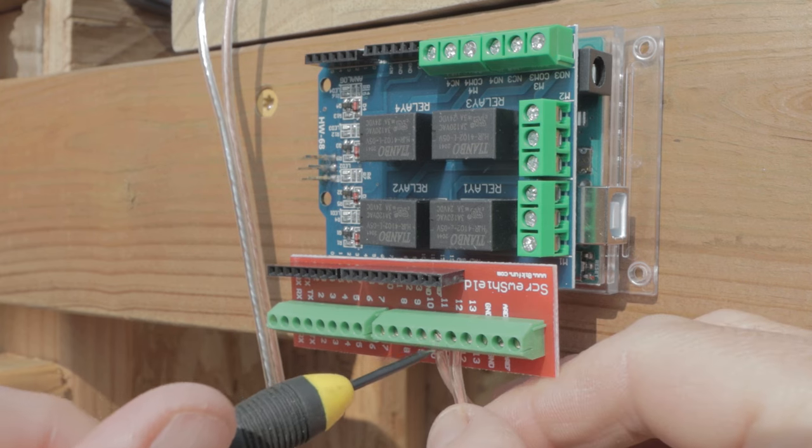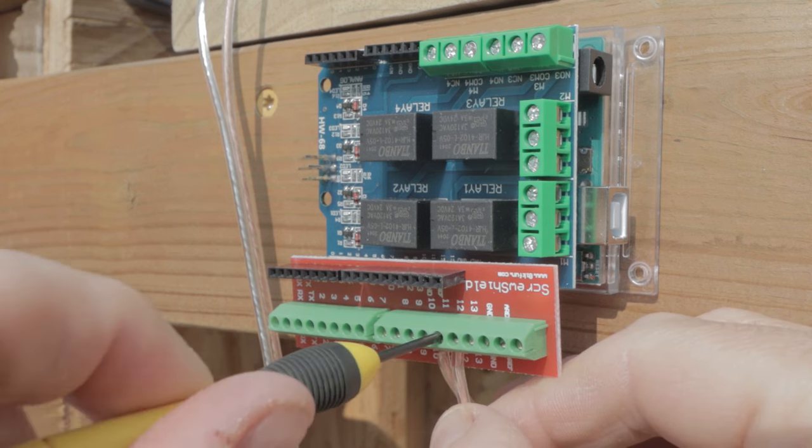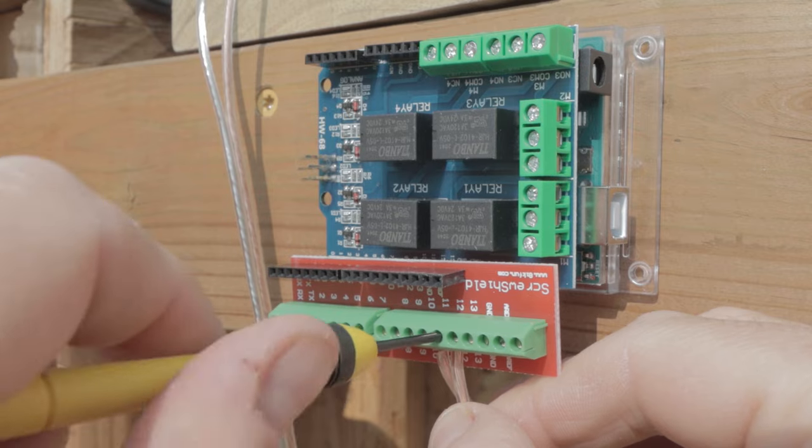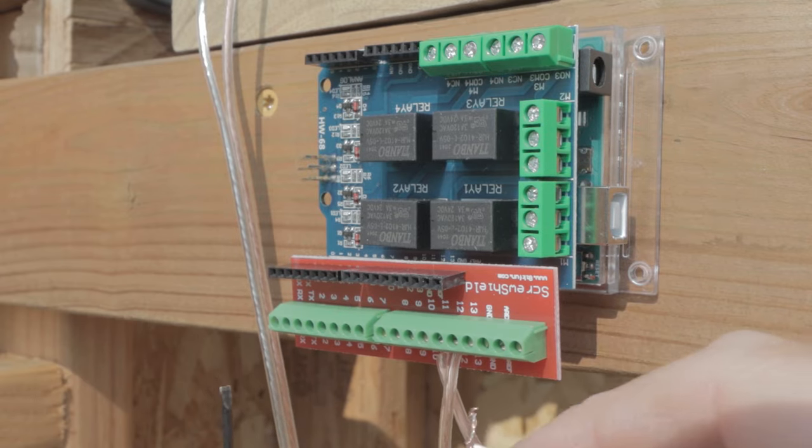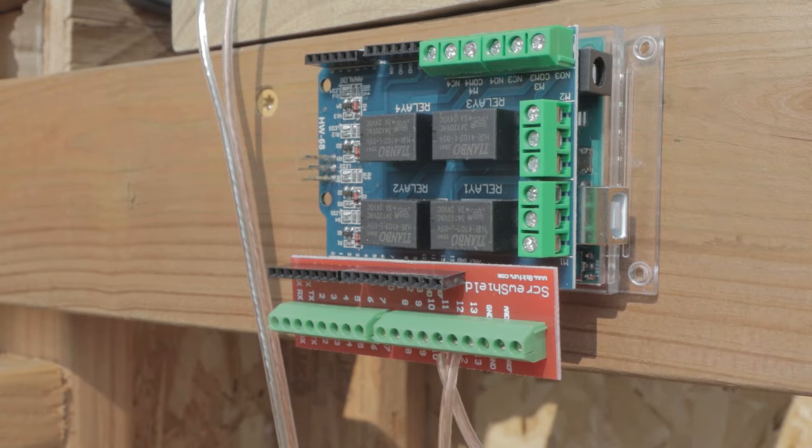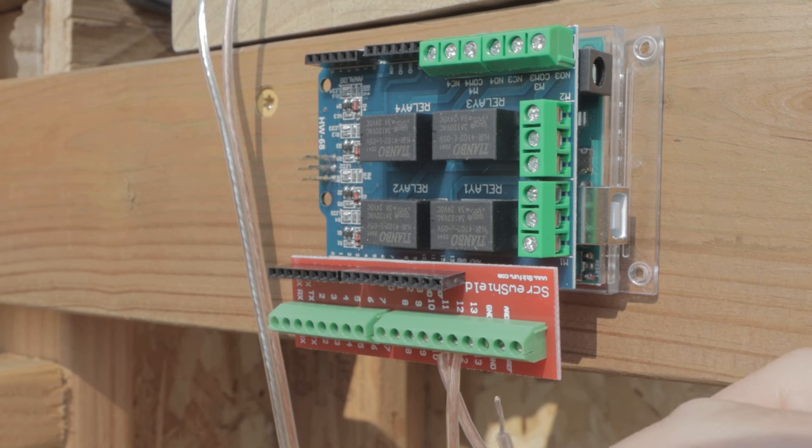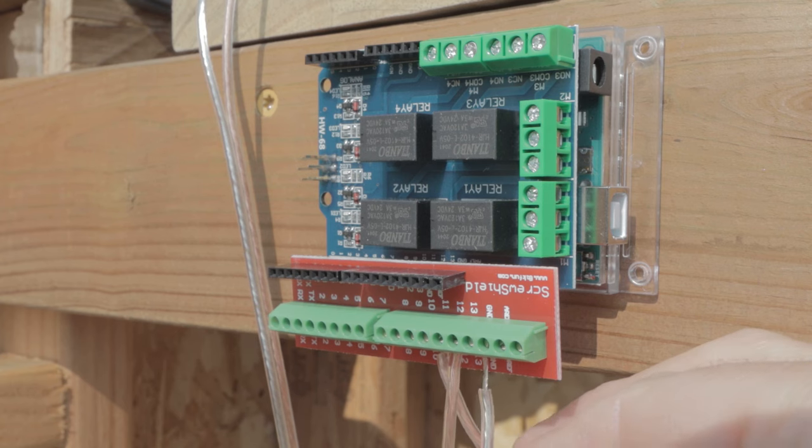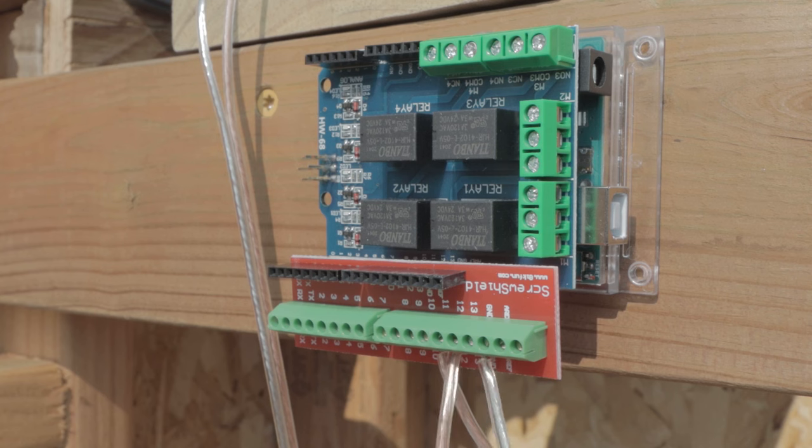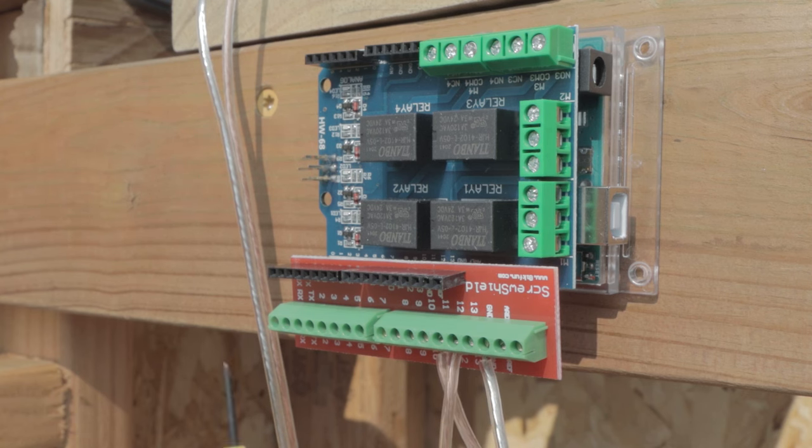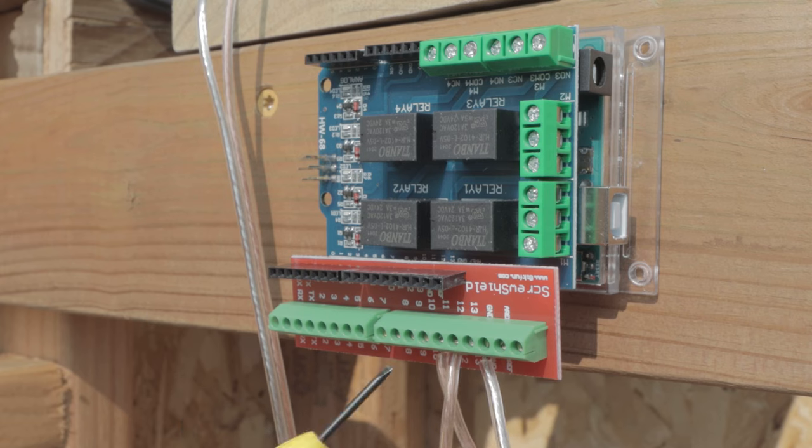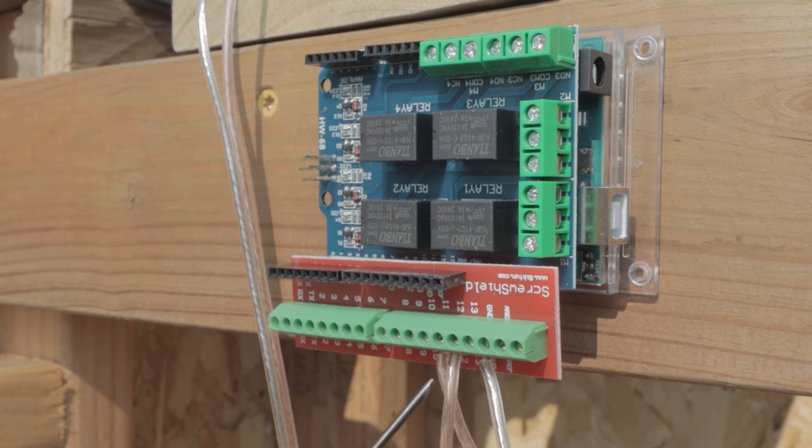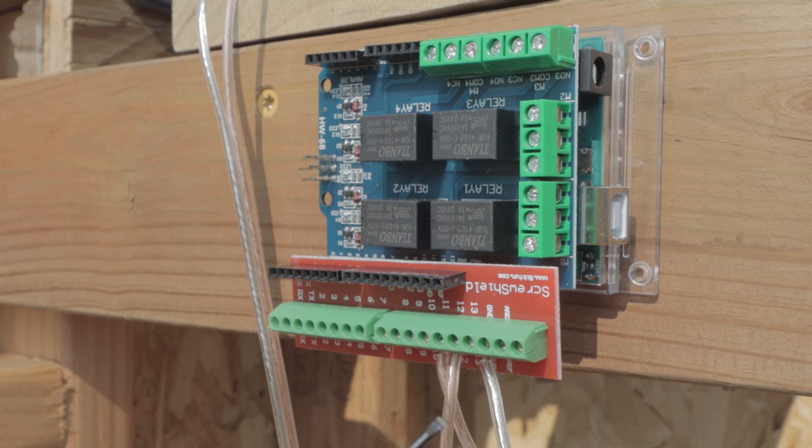Okay, our next sensor is going to go into 12. This sensor is the sensor for when the roof is supposed to be closed. Our cable for the sensor inside, and close it up, tighten it up. And lastly, we want to connect our ground to where it says ground. So these are our only inputs. We have three inputs. Number 11 is going to the roof open sensor. Number 12 is going to the roof closed sensor. And ground is going to ground. And the ground on the other side is connected to both grounds on the sensors.